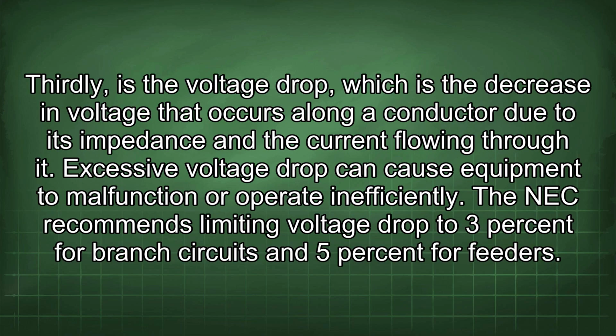Thirdly is the voltage drop, which is the decrease in voltage that occurs along a conductor due to its impedance and the current flowing through it. Excessive voltage drop can cause equipment to malfunction or operate inefficiently. The NEC recommends limiting voltage drop to 3% for branch circuits and 5% for feeders.